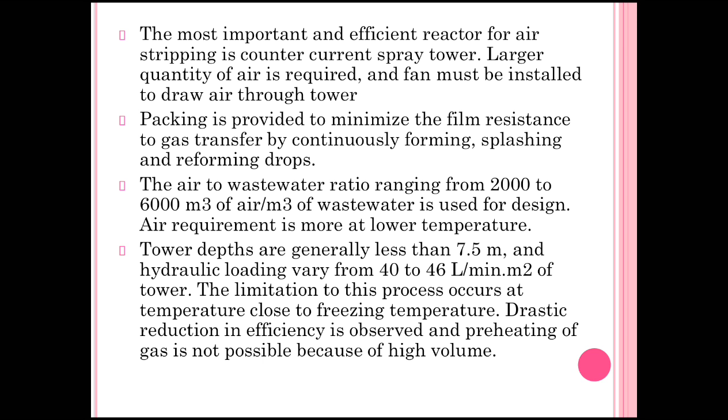Air requirement is the most at the lower temperature. Generally the tower depth is less than 7.5 meter, and hydraulic loading varies from 40 to 46 liter per minute per square meter of tower.